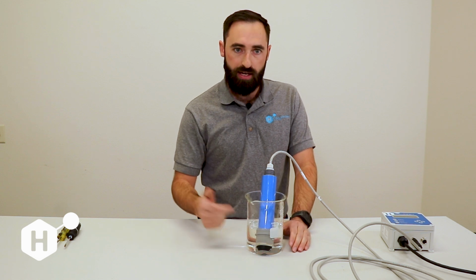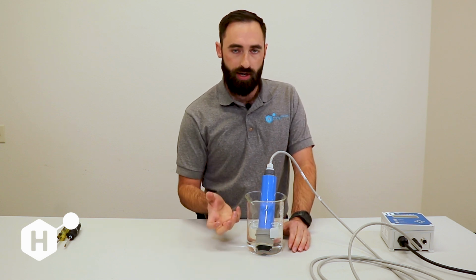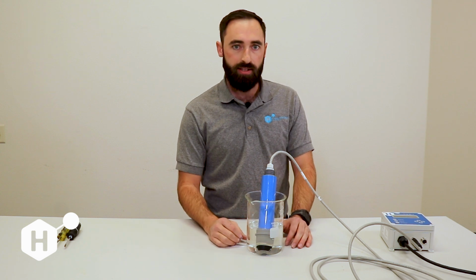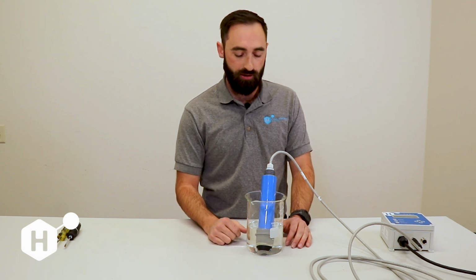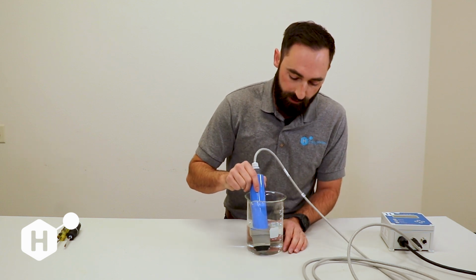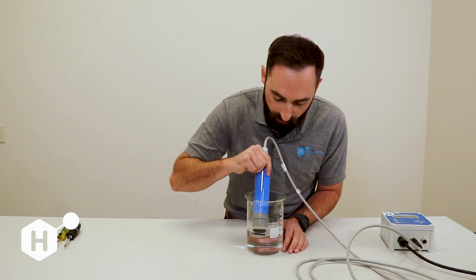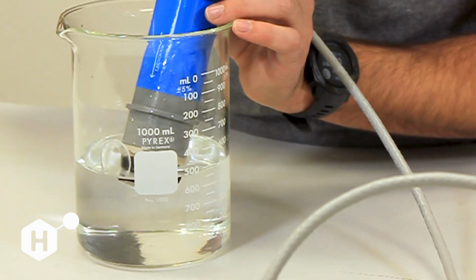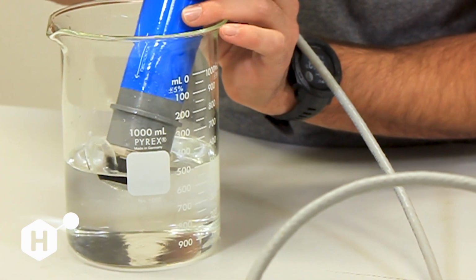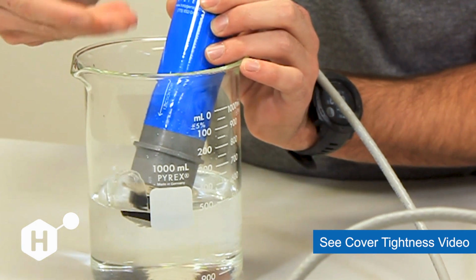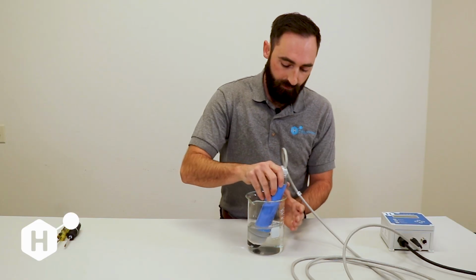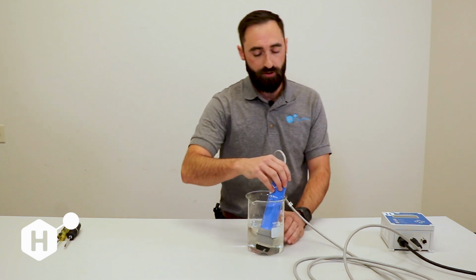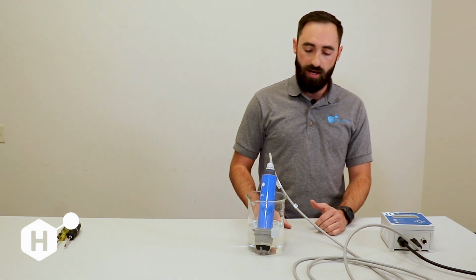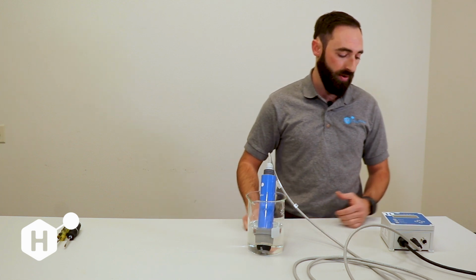You're going to want to do the startup procedure in water. As you can hear, that motor oscillates this direction a couple times, and what that's going to do is prime our sensor. By prime, I mean we're going to push out any air that's in the sensor cover and get water flowing across our measurement surface. The way you're going to know that this sensor is primed adequately is if you pull it a little bit out of the water, you're going to be able to see the water coming out of that ejection port. This is normal operation. If our sensor is not doing this, you are not adequately primed, or the sensor cover is on too tight and that impeller is being bound. So looking at this, I now know that my sensor is mechanically working normally. I have a good primed water stream, and I'm getting representative sample flowing across the measurement surface.